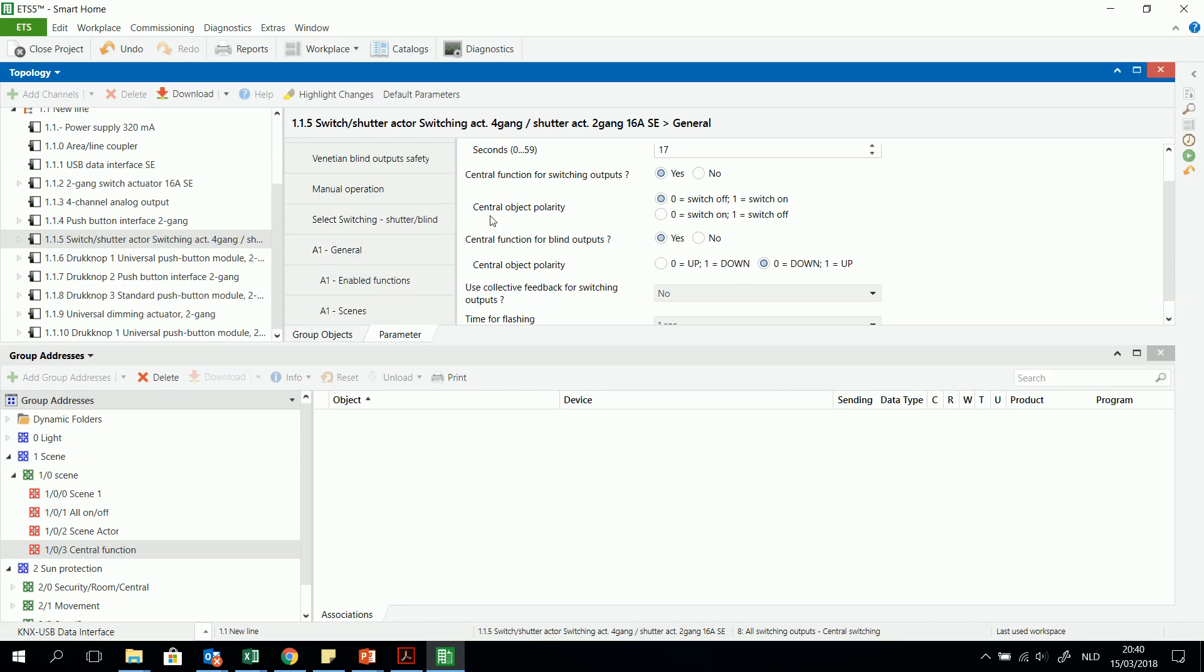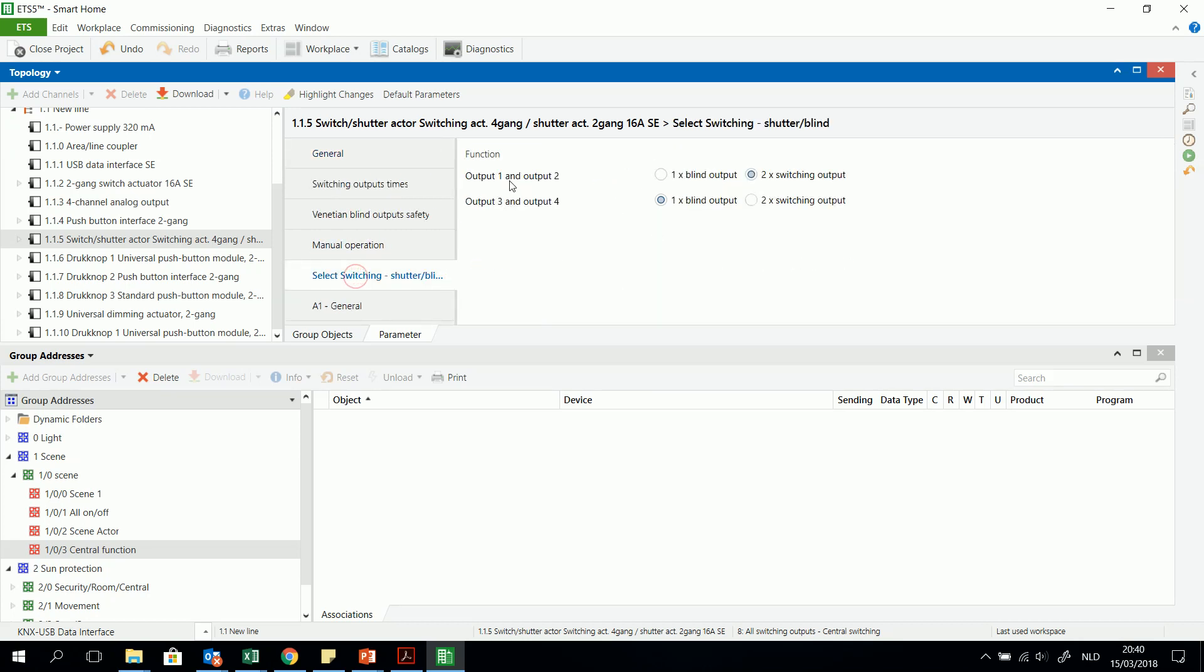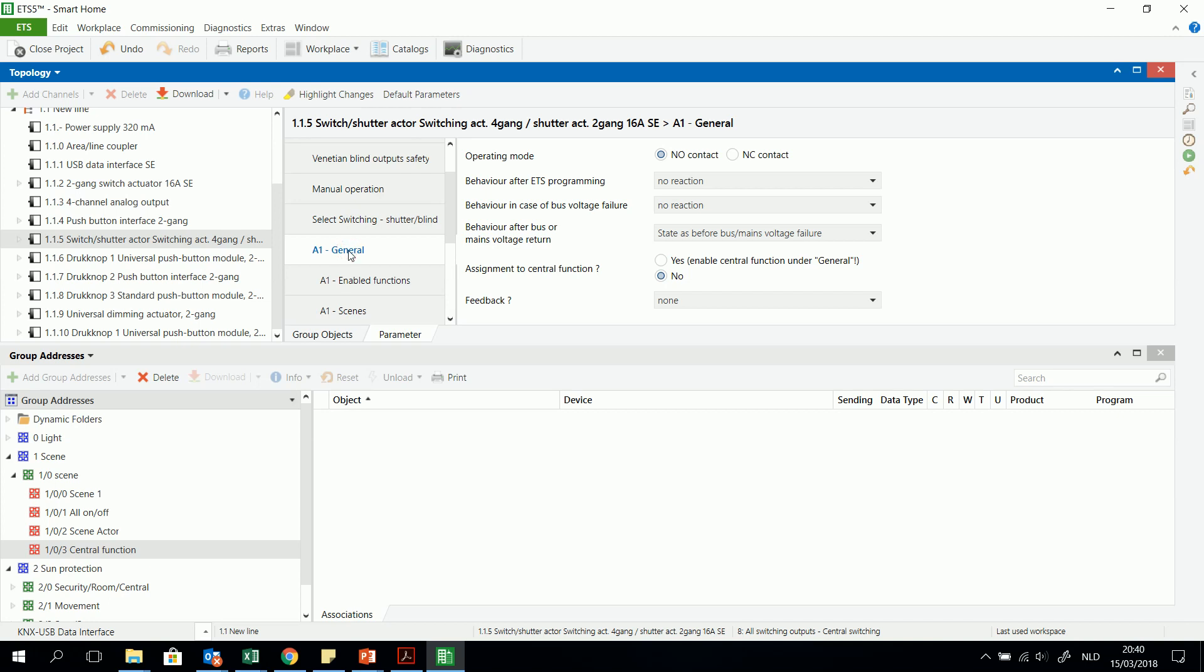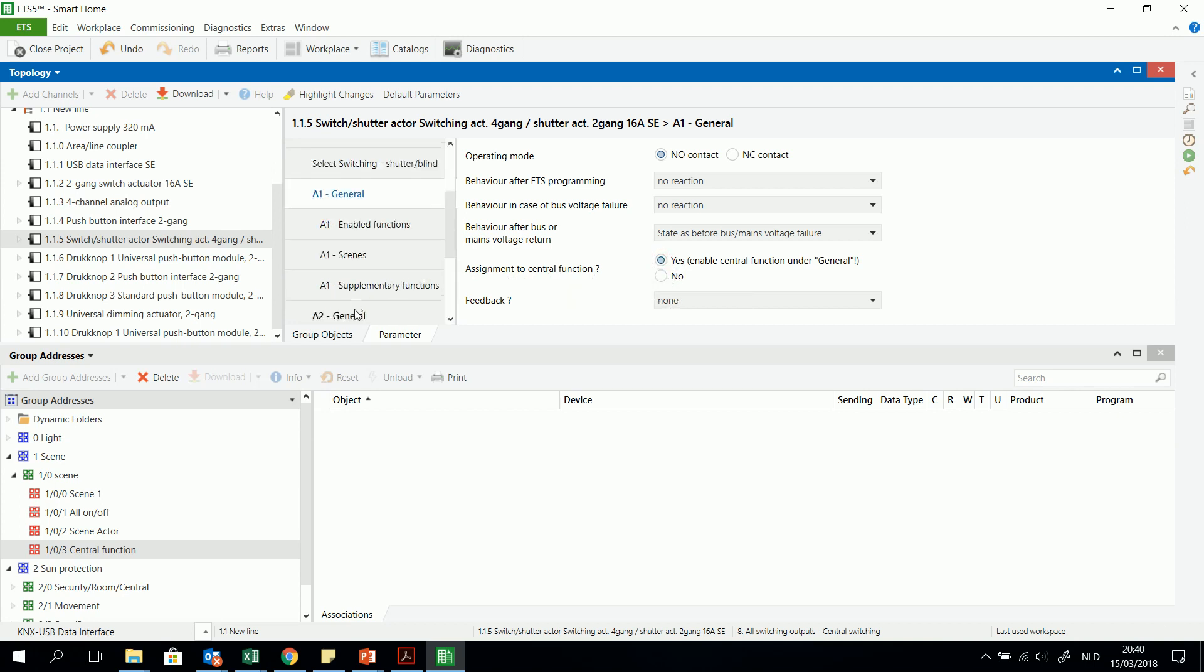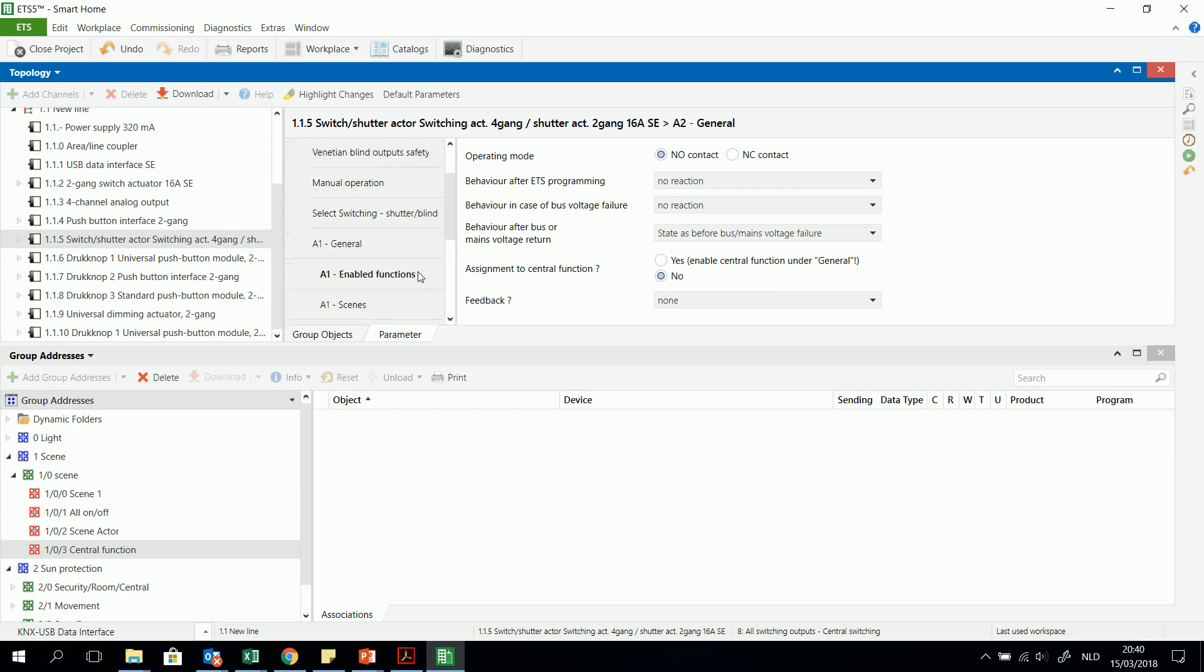It is not because you already activated the central function, for example the switching objects. In this case I have output one and two for switching output, and three and four together for one blind. For example output A1, I wanted to assign also to the central function. Because otherwise when I kept here to no, for example also with the A2, the second output, this means that there wouldn't be any reaction even if I program it well.